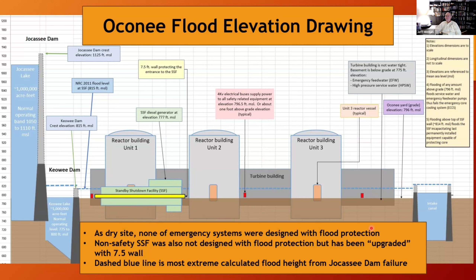And they built it primarily to take care of vulnerabilities from fires and tornadoes. They still weren't concerned about flooding, so they didn't build the SSF to deal with flooding. So if they had water level above grade, that would go into the basement of the SSF, which is where the diesel is for the SSF. In the 80s, they finally acknowledged to themselves that they had a flooding issue, and they built a wall around the SSF. And in around 2008, 2010, they extended that wall a little bit higher, to about 7.5 feet.